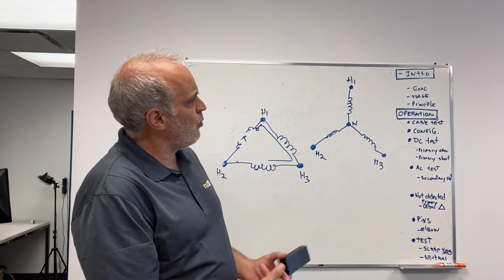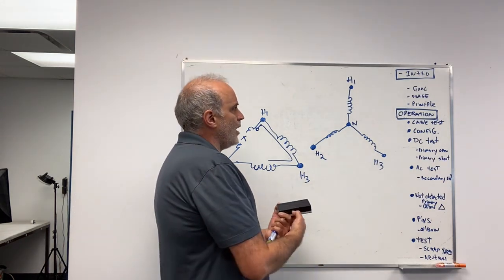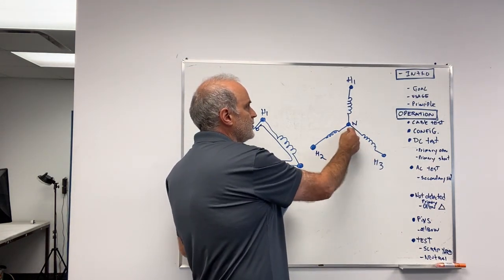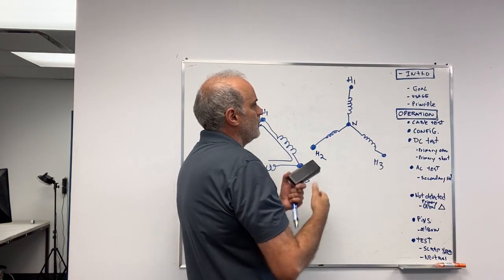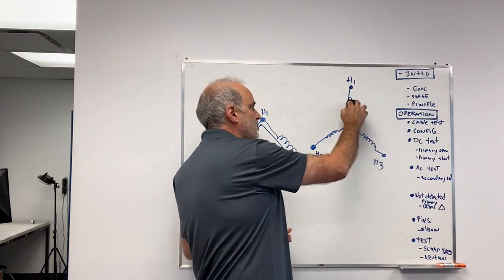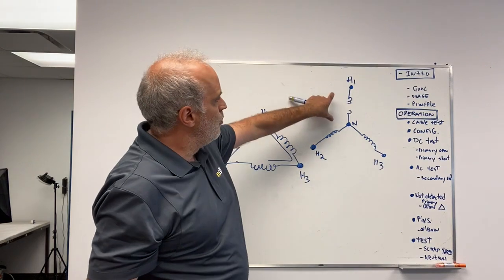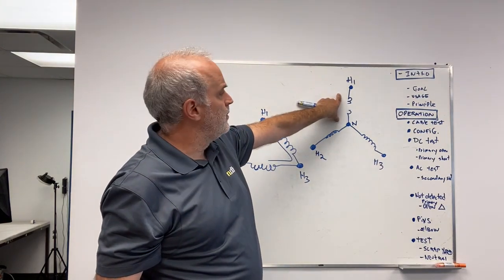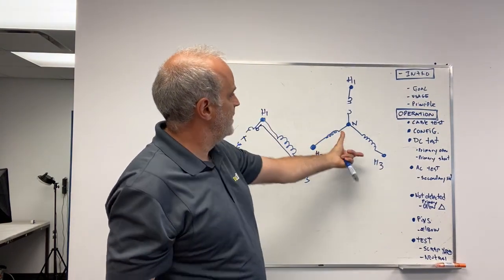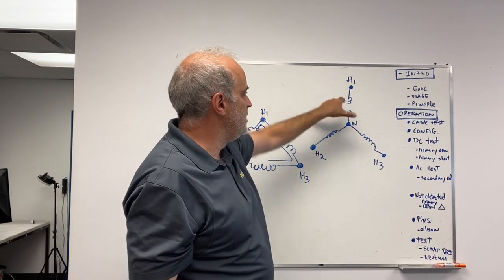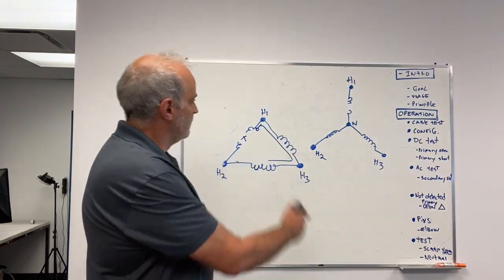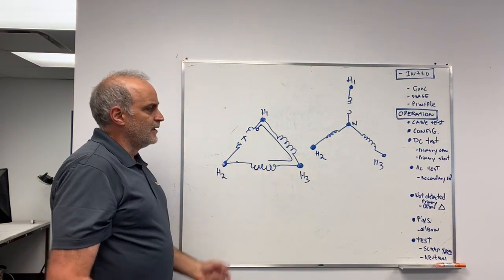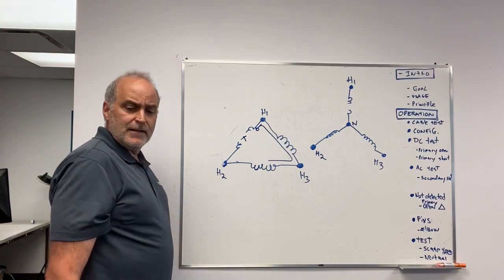Totally different with YN. If YN, because we're connected on the neutral, so if one winding is open, I'll know it because I'm taking measurement on each winding. Things are different in delta.